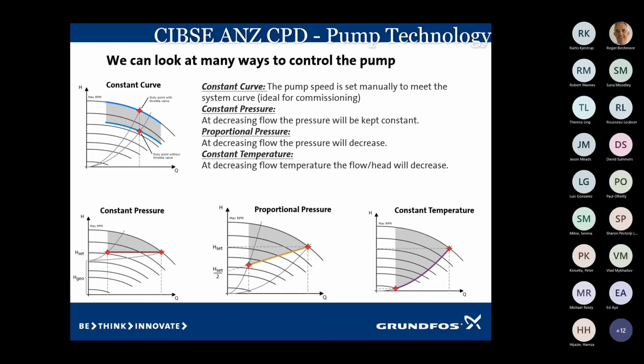We can look at some different types of control modes. Constant curve, that's the one there, we can actually just manually adjust the speed of the pump. So you can say to the pump, okay, I'm just going to manually drop you from 100% down to 85%. And then if I've got the right flow and head in the system, and then I'm happy, it's all go.